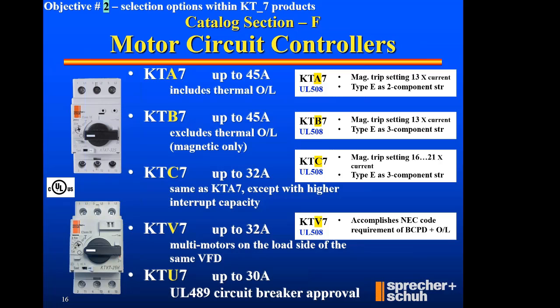Okay, on a B, we took out the overload. That KTB is somewhat analogous to an MCP circuit breaker in that, yeah, it's got magnetic sensing on the inside. However, there is no overload protection to it. What we've done to KTB is merely remove the overload out of it so that an overload can be attached to the load side of a contactor, creating a 3-component type E kind of a starter. Well, heck, why would we do that? Why would we take the integral overload out of the controller and give it down below?